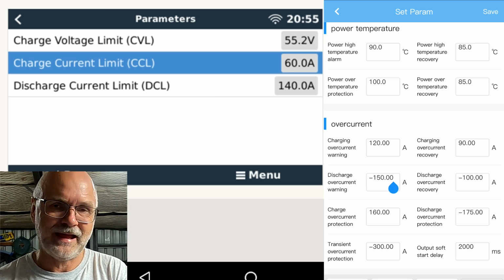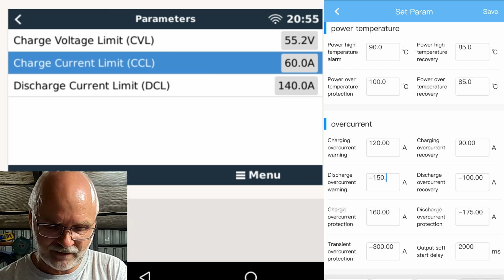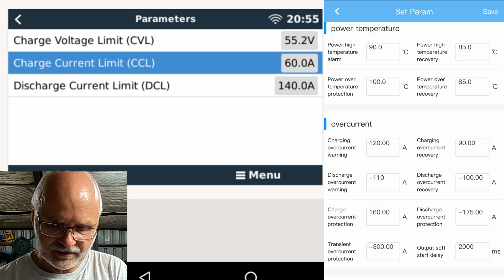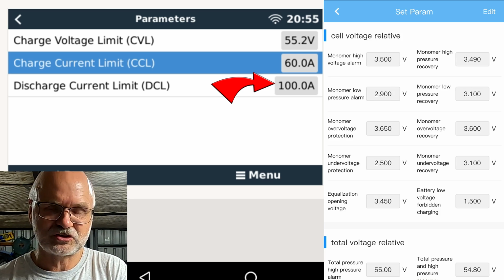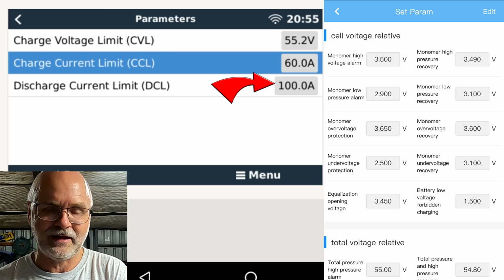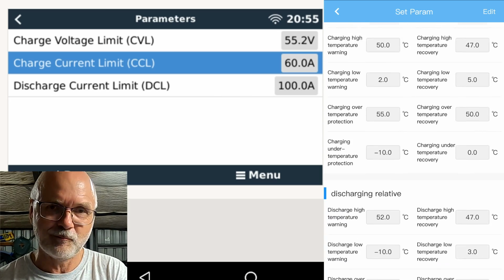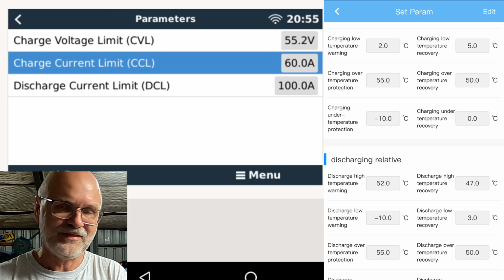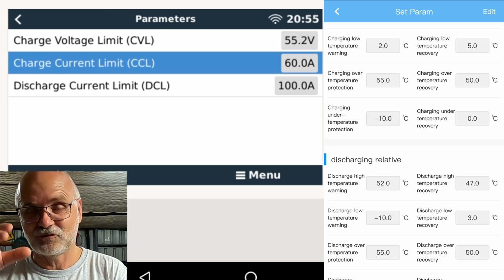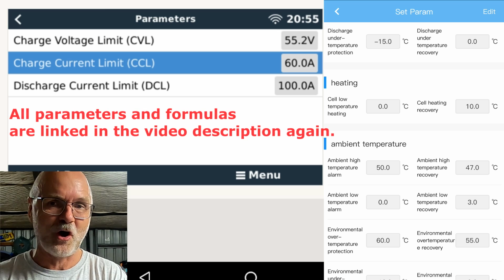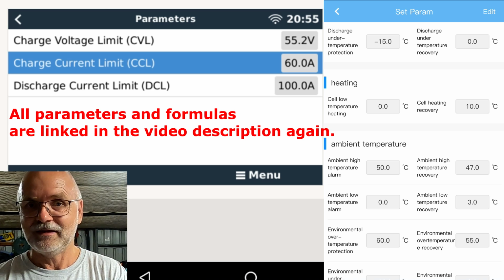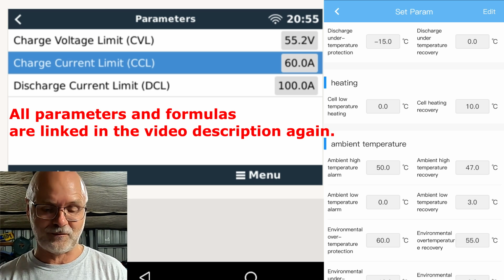So if you want to set 100 amps as discharge current, obviously you have to add these 10 amps. So you set this one to negative 110, click on save, and we can see it changed in the Victron system immediately to 100 amps. So it's always 10 amps more in the BMS what you have to set than what you actually want the battery to be discharged with. I don't make this up, guys. This is just what SEPLOS came up with. These are the parameters and formulas you need to know to change the settings in the BMS, to change the settings actually in the Victron system so they can follow the request from the BMS.